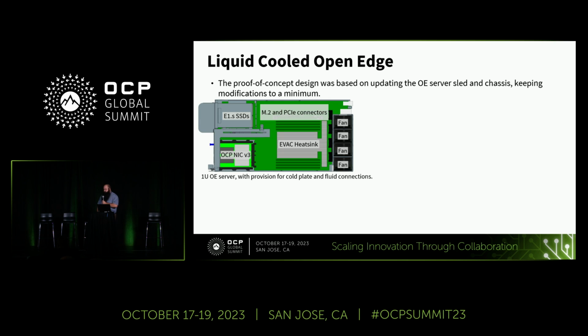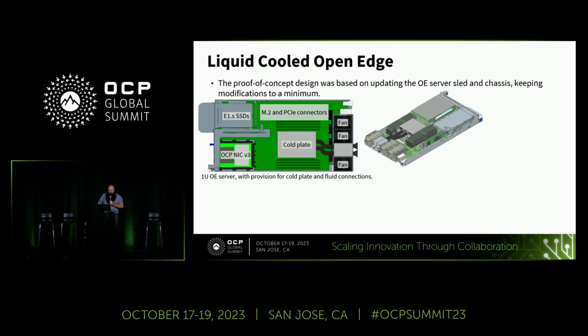We tried to build on some of the modularity that's already been put in the system itself. This is what the default server sled looks like. You'll see on the right there are 4 fans, and basically there's a heat sink. So what we looked at doing is replacing that heat sink with a cold plate, and then we took out one of the fans and put in a set of manifolds.